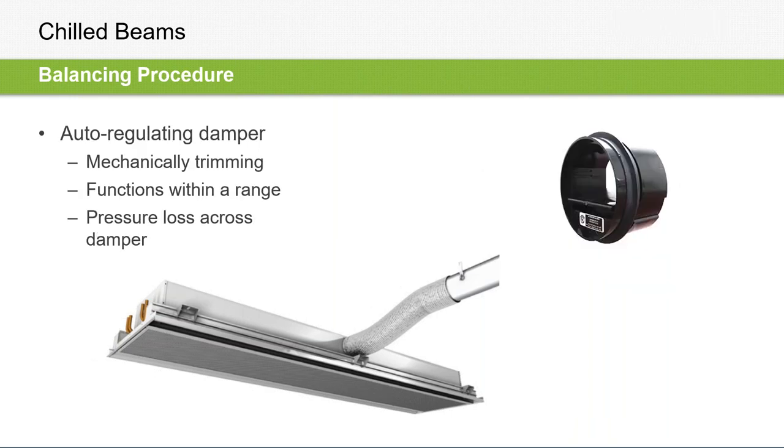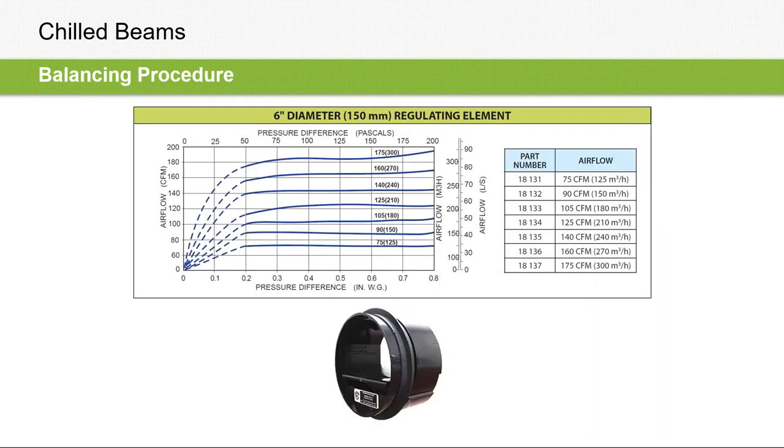And also one we see pretty regularly is the auto flow regulator here, which will essentially self-balance within a given pressure range. So between 0.2 inches and 0.8 inches of static, we find this holds the CFM fairly regularly. So you can see that in this chart here. Going up below the 0.2 inches of static, it's a pretty steep curve. And then it really flattens out between 0.2 and 0.8, which is exactly the operating range that we're going to see in most beams.